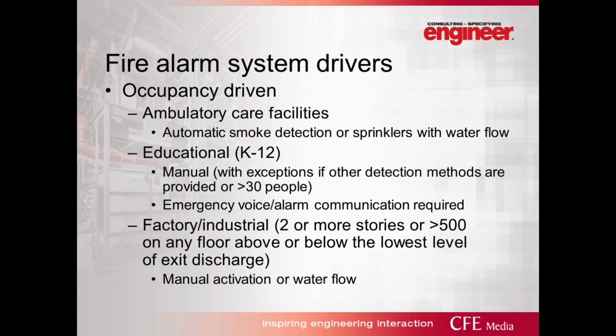Okay, so let's move on. Ambulatory care facilities, okay, automatic smoke detection or sprinklers with water flow is what is required to drive the fire alarm system in that type of occupancy. Educational occupancies, again, we have manual with exceptions if other detection methods are provided. So if you have water flow or smoke detection, you might have smoke detection as a risk management tool. You can forego the general application of manual fire alarm boxes. But there is a requirement that's come into the code in the last few cycles for emergency voice alarm communication. So prior to a few cycles ago, you could use sounders, but new construction now is requiring emergency voice.